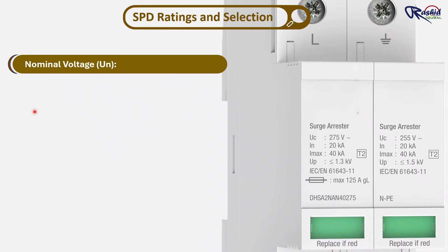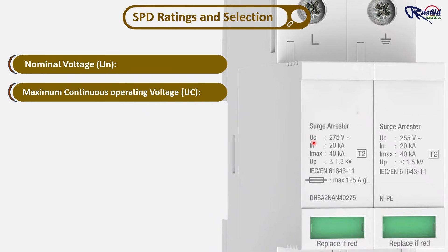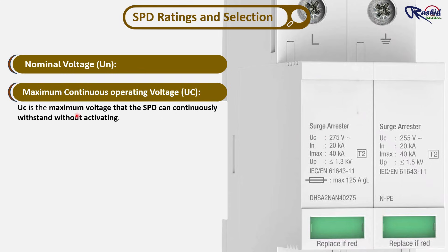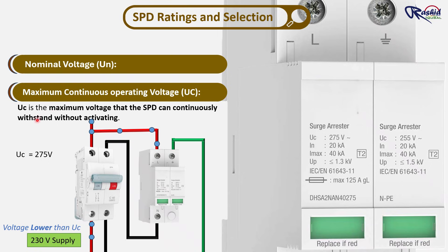Number 2 is maximum continuous operating voltage, UC. This is the highest voltage that the SPD can continuously handle without activating. In other words, as long as the supply voltage stays below the UC rating, the SPD remains inactive and lets power flow normally. It only activates when the voltage goes higher than the UC rating, because it should react only to a surge and not during normal operation.